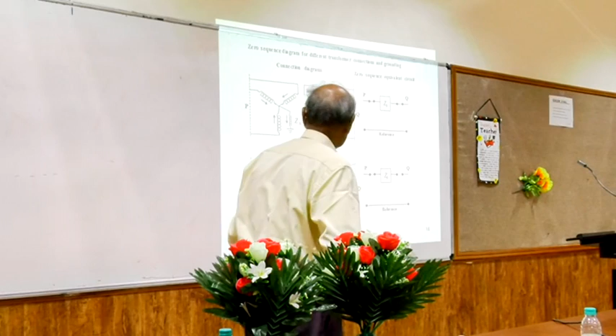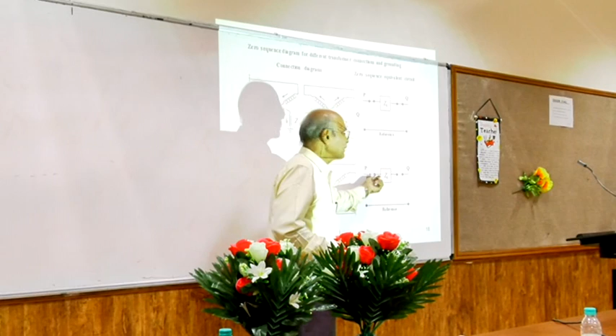Now let's come here. This is ground isolated. That means zero sequence current cannot flow through that. Just now, what we saw is that the primary cannot have current if there is no current in the secondary. So now I make this one open, and this one I close, because in case there is a return path provided by some other component, then it may carry current. To indicate that, I connect it and leave it. Otherwise, you can also say this is hanging. There is no current through this transformer as it is. That is what I intend to show. So this is for the star case.